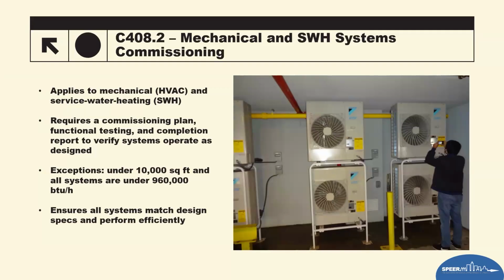There are a few cities in Texas that have done that already. But this section basically strengthens the commissioning report for both mechanical and service water heating. Projects must develop a commissioning plan early, execute what's called functional testing for all major equipment, and then provide documentation, preliminary and final reports that verify the system performs as intended. Note that the update exemption threshold from the building is less than 10,000 square feet with a combined system capacity of 960,000 BTUs may be exempt.